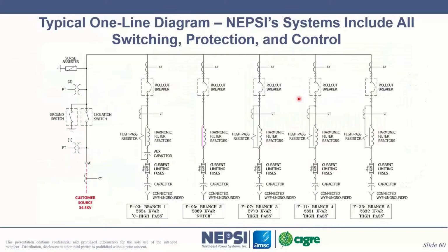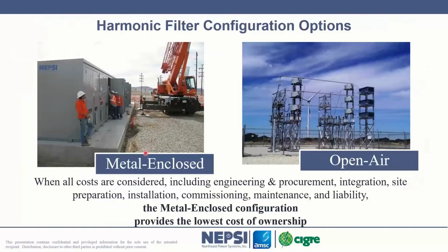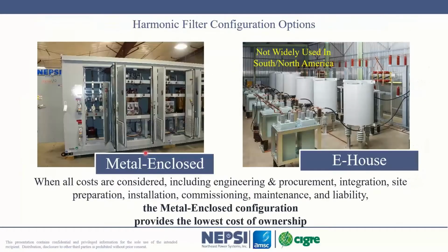If we go back to our original design here, you can see we have multiple stages. In this case, we're switching in basically 5 megavar steps, 5,600 kvar steps at different branches, but we have different types of filters and different tuning points. So the long answer to this is the harmonic currents can change, but the harmonic filter system must accommodate those changes.